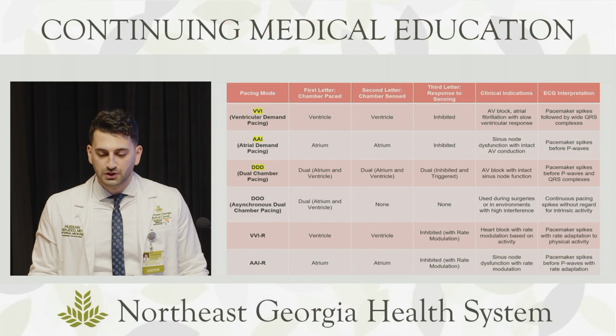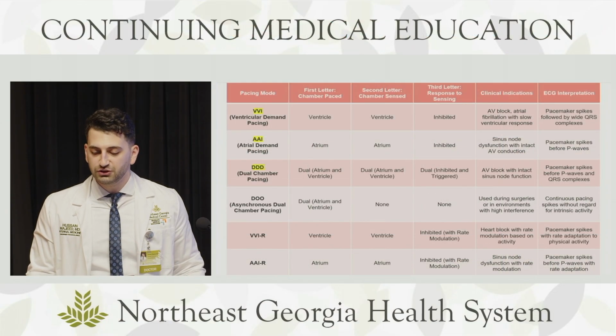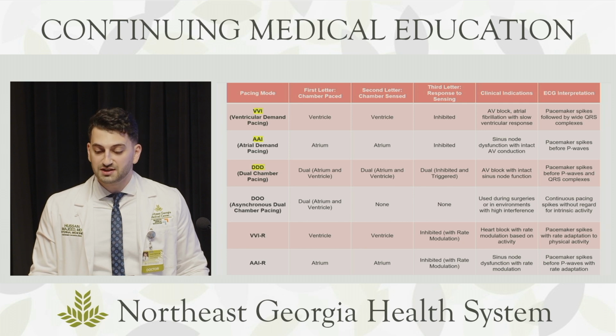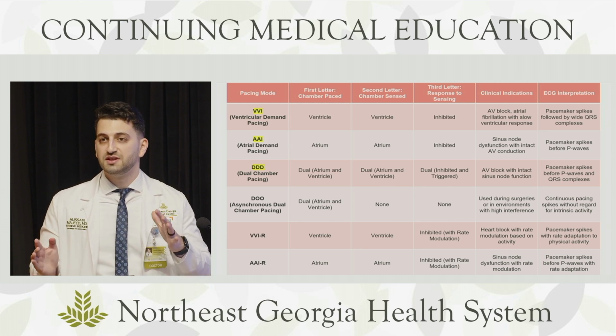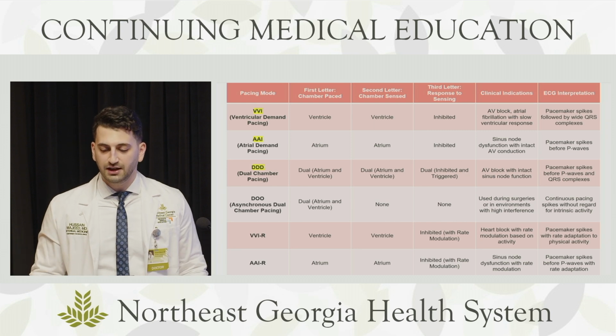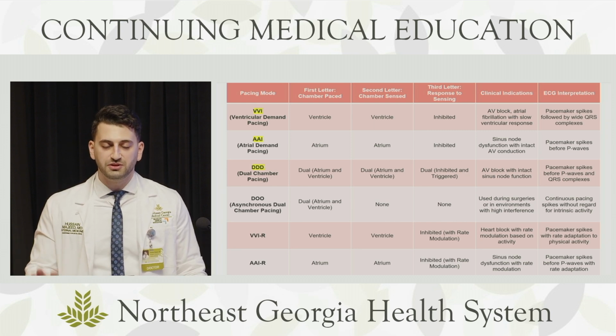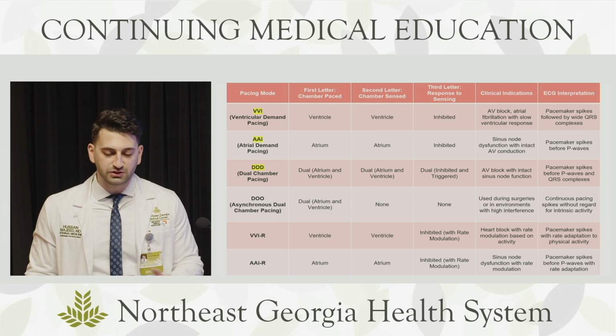Basically the ventricle is paced and the pacemaker is inhibited if it senses intrinsic ventricular activity. You can see that mostly in patients with atrial fibrillation and slow ventricular response. AAI is also a pretty common one. The atrium is paced, and the pacemaker is inhibited if it senses the intrinsic atrial rhythm, if the SA node is still functioning. So that's really useful. DDD is also one of the most common ones. Both the atrium and the ventricle are paced, and both of them are sensed. That really ensures that there's significant synchrony. The pacemaker takes control of everything, and it's used in AV blocks with intact sinus node function, where there's an issue with the conduction from the A to the V.